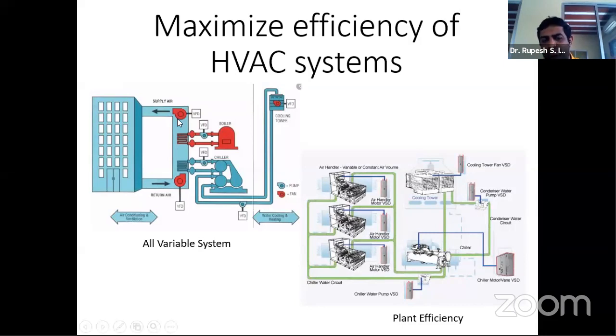We have taken care of the low side, the process itself, my AHUs and cooling coils, and on the high side, the chillers, the cooling towers, and the pumps. Finally, can we have a very low plant efficiency in terms of kilowatt per ton? We have seen buildings with a plant efficiency of even 1 or 1.5 kilowatt per ton, but today there are also buildings which could be designed at a plant HVAC efficiency of about 0.5 kilowatt per ton.